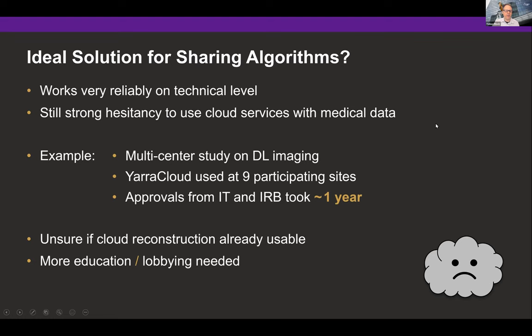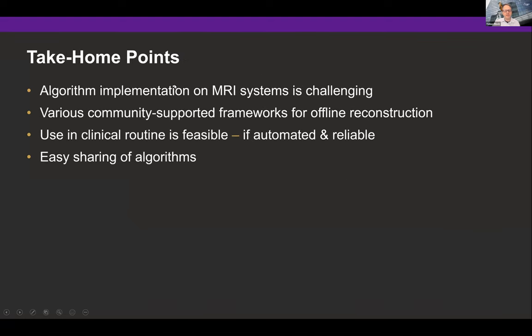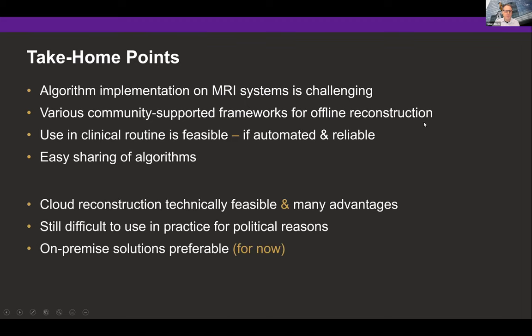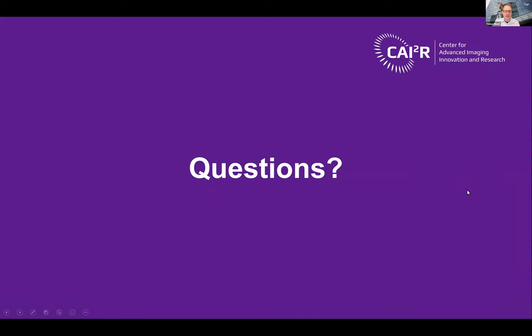To give a few take-home points: implementing algorithms directly on the MRI scanner is quite challenging and I wouldn't necessarily recommend it. However, today there are very good community-supported frameworks available for offline reconstruction, and it is actually possible to use offline reconstruction in clinical practice if the processing is automated and reliable — it also makes it very easy to share reconstruction algorithms with the research community. Cloud-based reconstruction is also feasible nowadays and works very well with many advantages, but at this point it's still quite difficult to use in practice because of political issues. My recommendation would be to still go with an on-premise solution for now. I'm happy to answer a few questions.